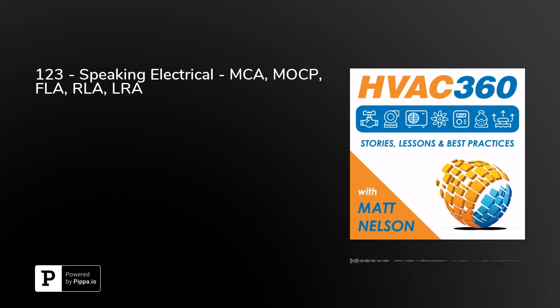The one thing that is noted, because you can calculate these things, is that the FLA is typically 80% of the MCA. In other words, the conductor wants to be loaded only to 80% of the circuit ampacity. And usually you'll see a lot of these different percentages of loading for electrical equipment, electrical switchgear, all the electrical. You don't want to take a piece of electrical equipment all the way up to its nameplate. You want to back it down to 80%. Why? Because that's really the only way that you can allow for one more circuit, a little bit extra, for these different changes that happen in all buildings.